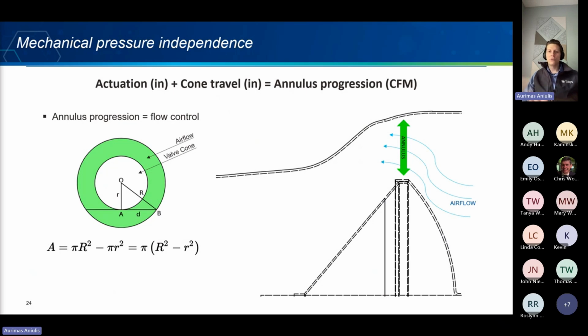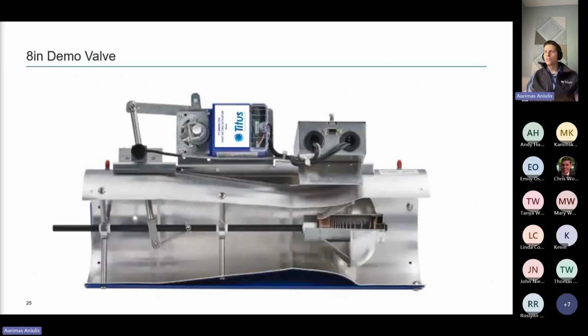Now, this is key when you read the specs and you see instant response. That's the instant response that they're referring to. They're referring to the cone spring mechanism instantly reacting to duct static pressure fluctuations, absorbing those pressure waves with this cone spring mechanism to reduce the open area of the annulus to allow the air to pass through, hence giving you a constant output on the outlet side of the valve. Now, this is our 8-inch demo valve. And you can see you've got your actuator, you've got your linkage, you've got your position sensor.